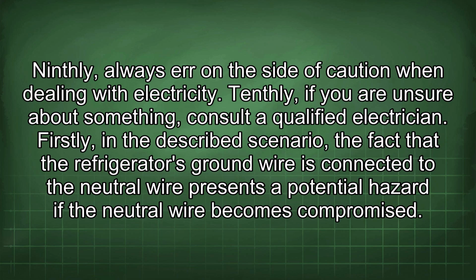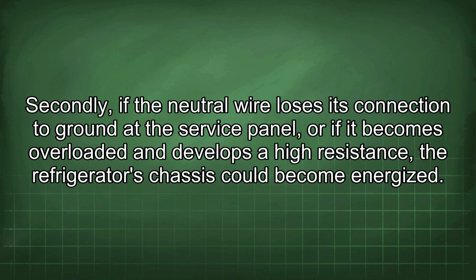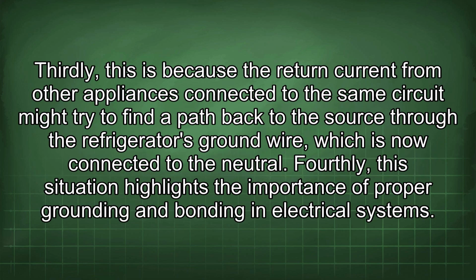Firstly, in the described scenario, the fact that the refrigerator's ground wire is connected to the neutral wire presents a potential hazard if the neutral wire becomes compromised. Secondly, if the neutral wire loses its connection to ground at the service panel, or if it becomes overloaded and develops a high resistance, the refrigerator's chassis could become energized. Thirdly, this is because the return current from other appliances connected to the same circuit might try to find a path back to the source through the refrigerator's ground wire, which is now connected to the neutral.